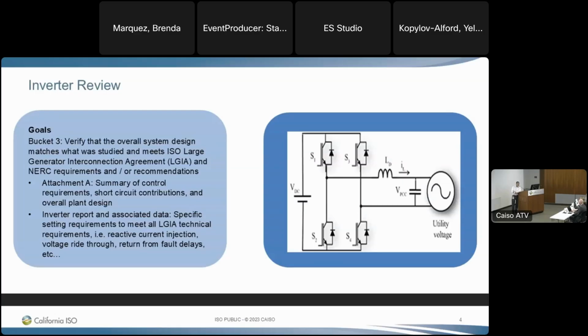Additionally, we look for an inverter report, which comes straight from the manufacturer. And when you see these reports, a lot of times they have hundreds and hundreds of settings. We look for very specific settings out of there, K factors for reactive current injection during low voltage ride through or high voltage ride through. We also look for ramp rates on return from faults. We look for any time delays associated with return from faults. And those are some of the things we look for.